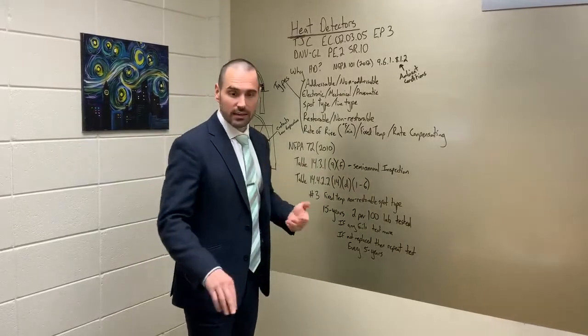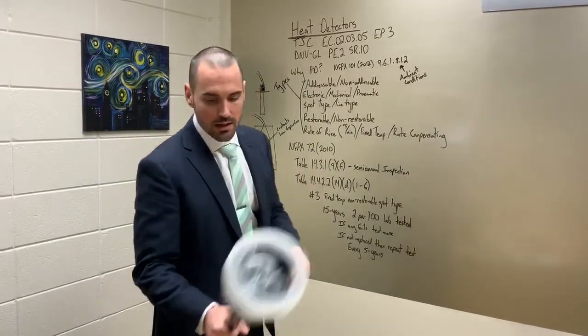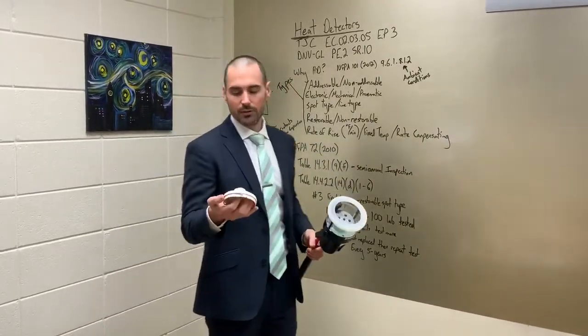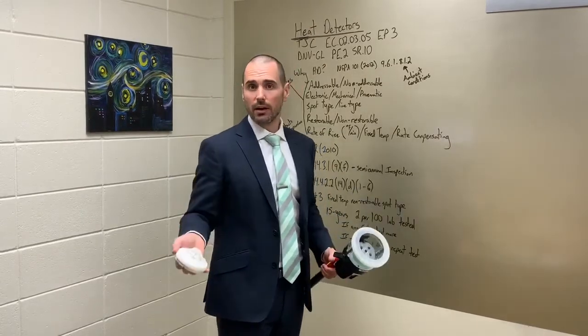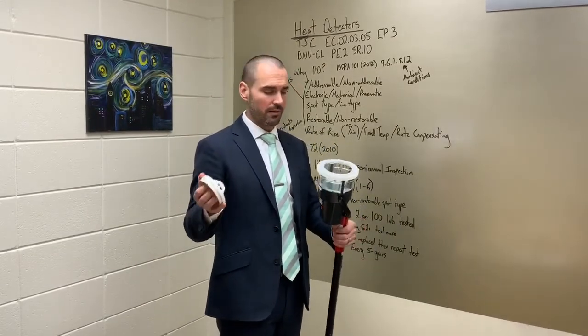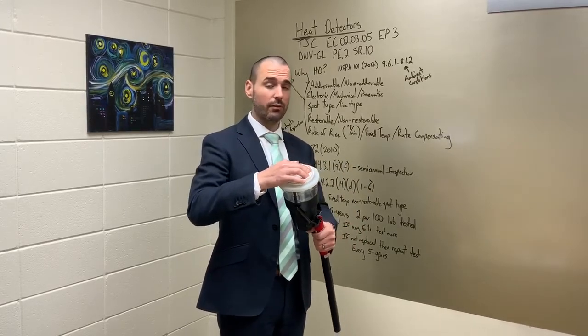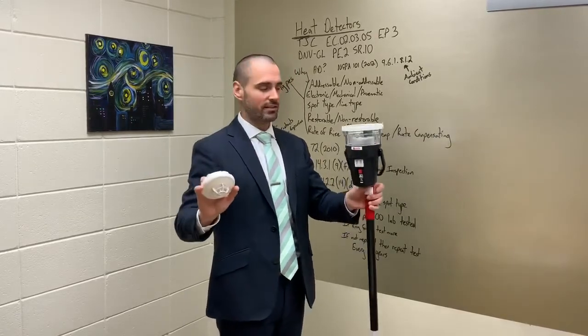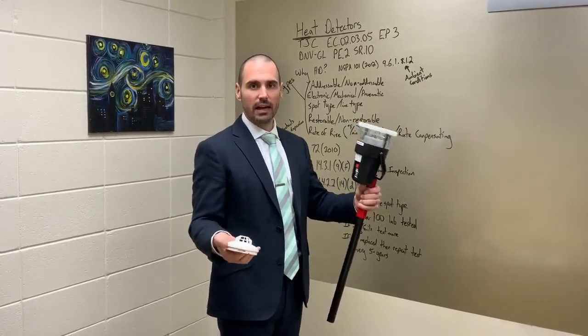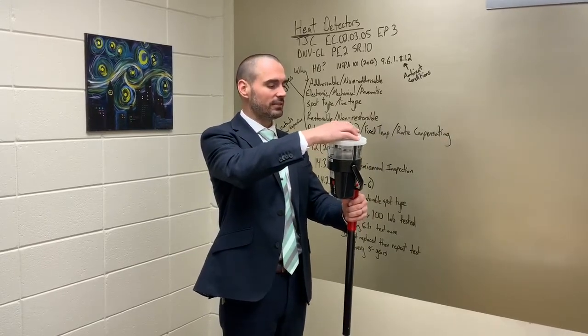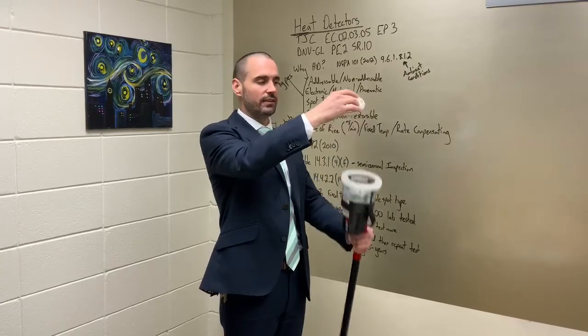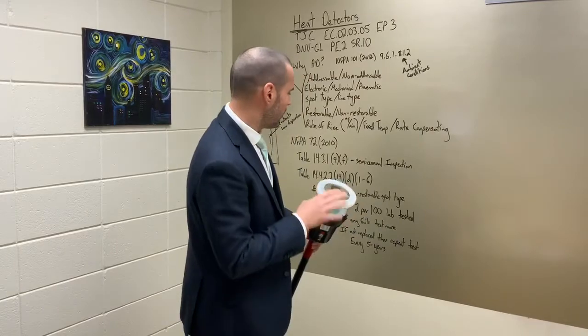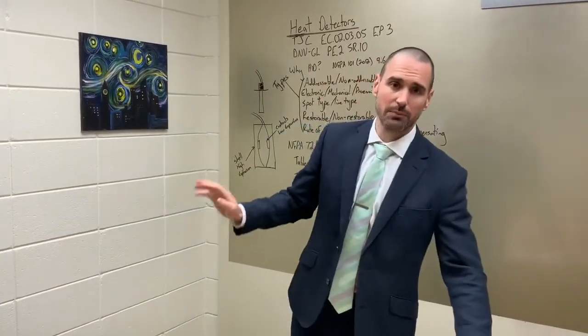And then for functional tests, just like smoke detectors, just like duct detectors, we have to do a functional test. Most manufacturers for your resettable, your restorable type devices tell you if you look at there and say use a hair dryer, use some sort of method to test. Some actually will say you can put it in water and whatever. Don't, there's way easier ways to do it. So there are several different testing type devices that provide heat. We'll test it and then when it's removed, you can reset the device. Those we don't really see problems with.